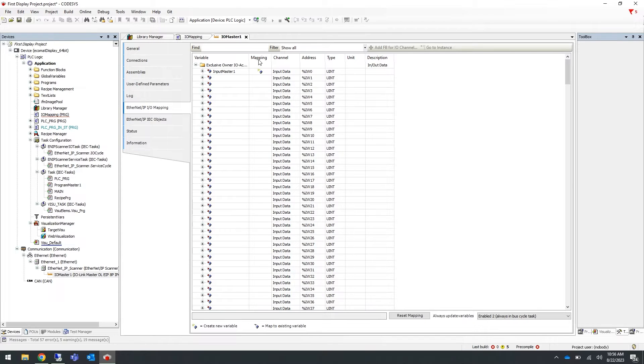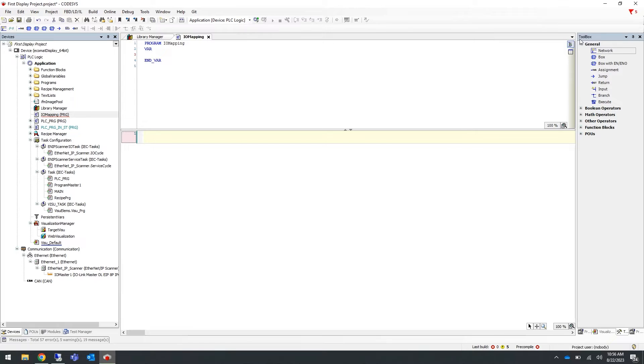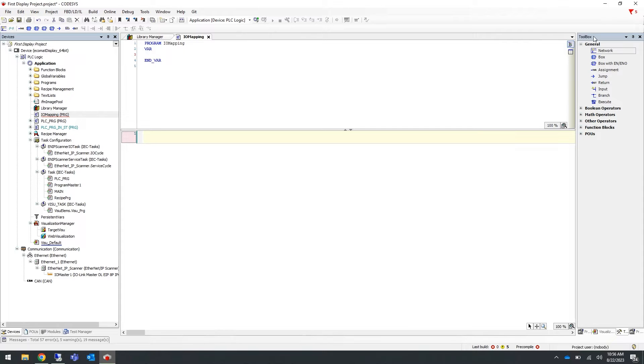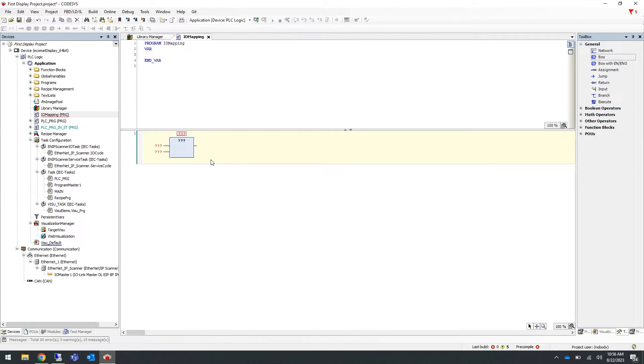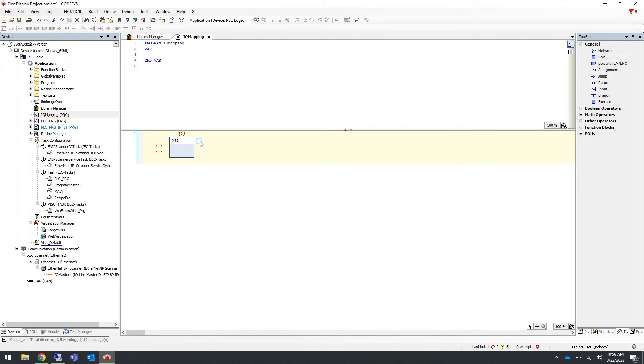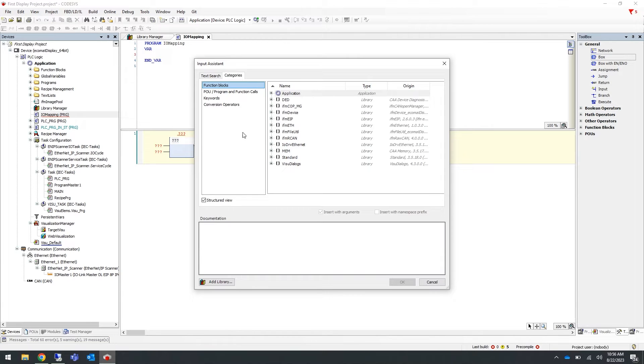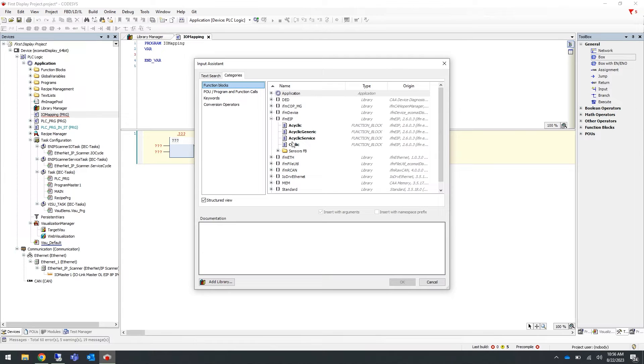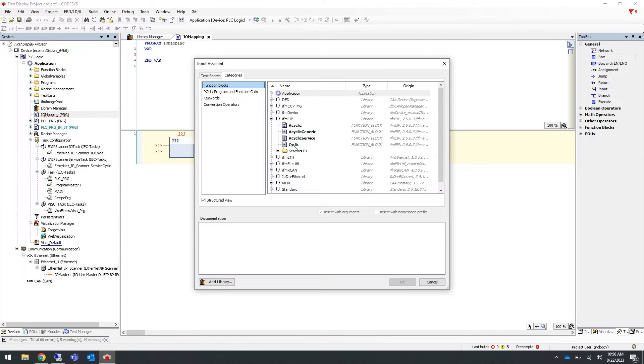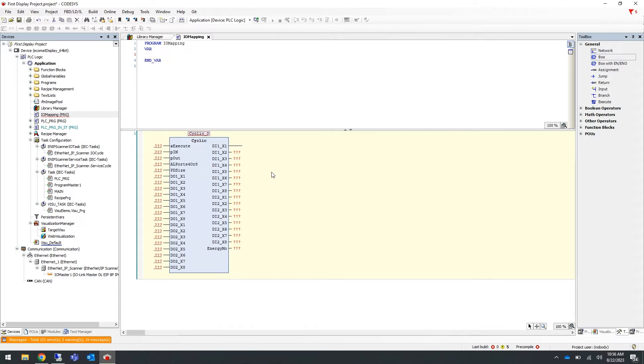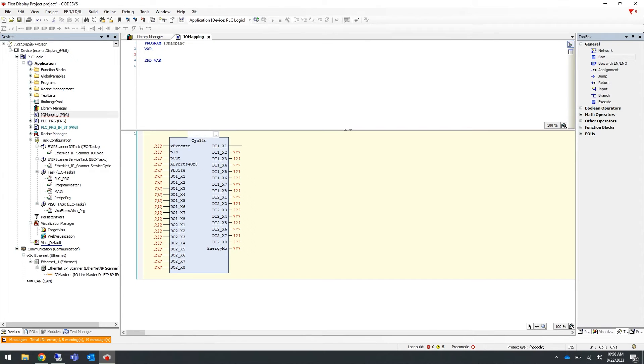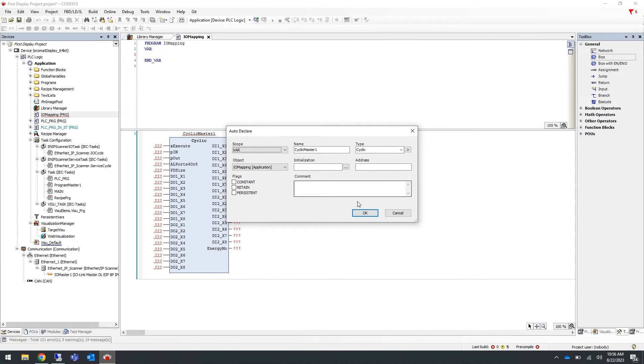Now if we go back into our program, on the right-hand side we have our toolbox and under the general menu, select the box and drag it and drop it into the first rung of our program. Select the three question marks within the box and then the three dots to the right. Go into the IFM EIP library and select the cyclic function block and press OK. Press enter and give this function block a meaningful name such as cyclic master one, press enter, and then press OK.